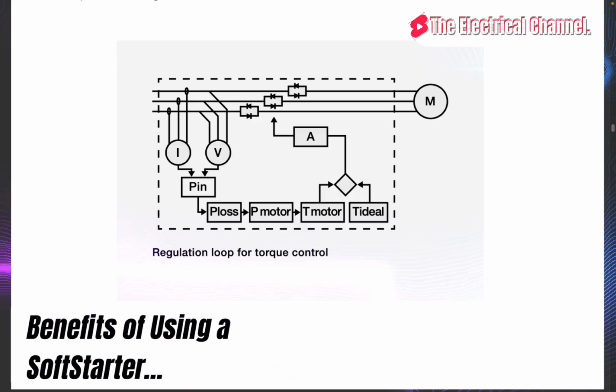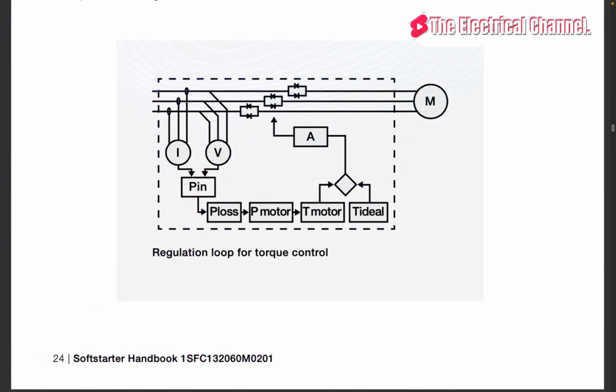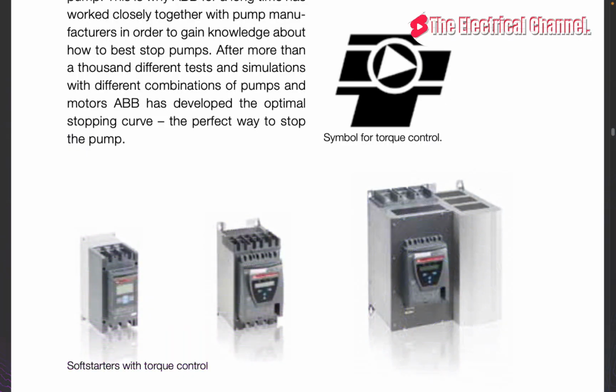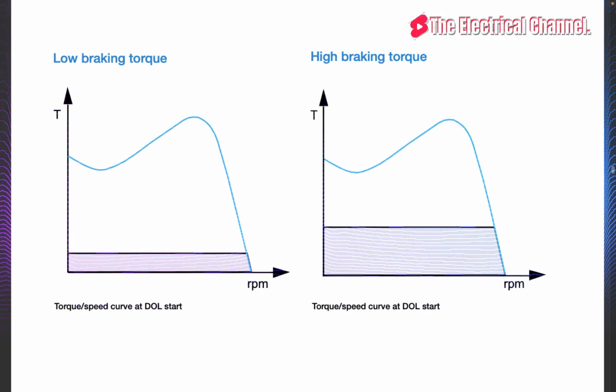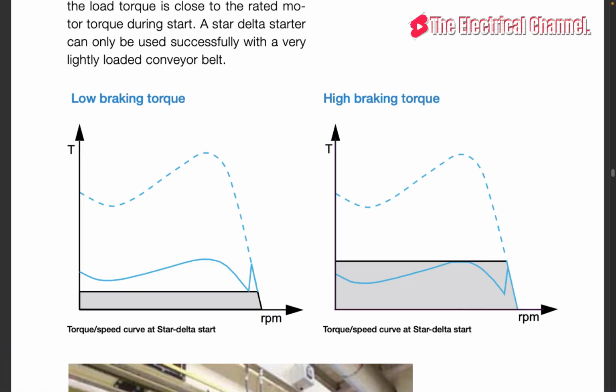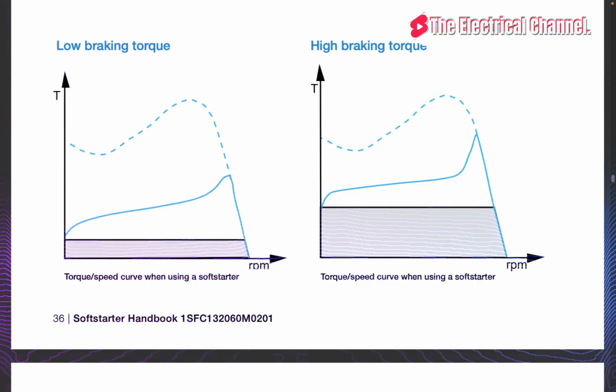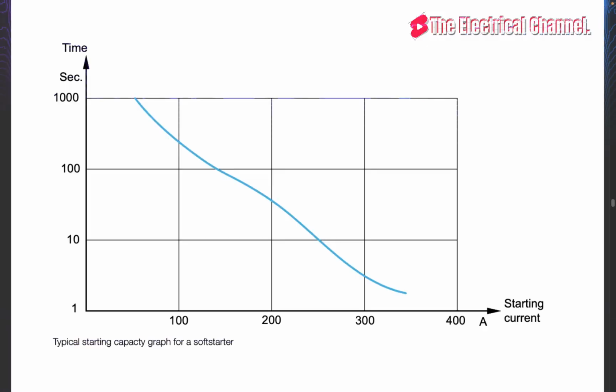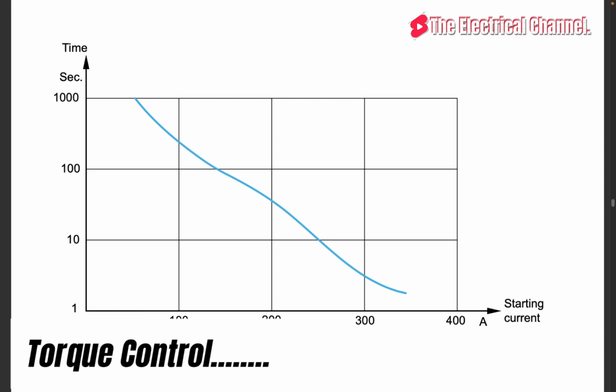Benefits of using a soft starter. The inrush current is reduced so that voltage drops on the network are avoided. The torque is reduced, which will decrease the mechanical stresses on the equipment and lead to a reduced need for service and maintenance, and also to a longer life of the equipment. Finally, by using a stop ramp, water hammering is avoided in pump systems, which will further reduce the stress of the equipment. Torque control.